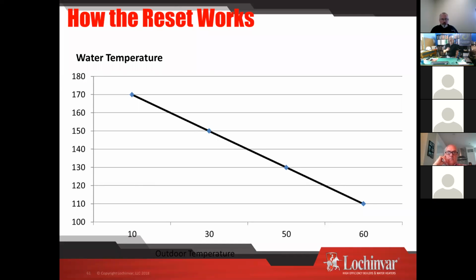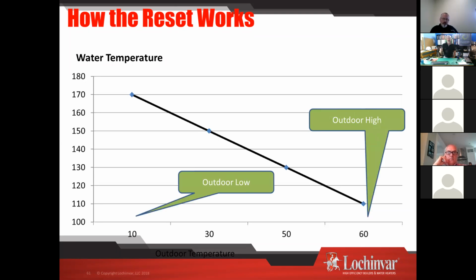Now, one of the things that in my original slide and why I had to change it, we always talk about 10 to 70. And we were setting the end of our curve at something like 70 or 68. But usually we have the heat off. So I recommend you bring that back, setting it basically at 60 degrees. So now I'm going to drop my water temperature down to the lower spot at 60 degrees out, and I'll be able to get those savings from 60 to 70 degrees or 68 degrees, wherever it is.